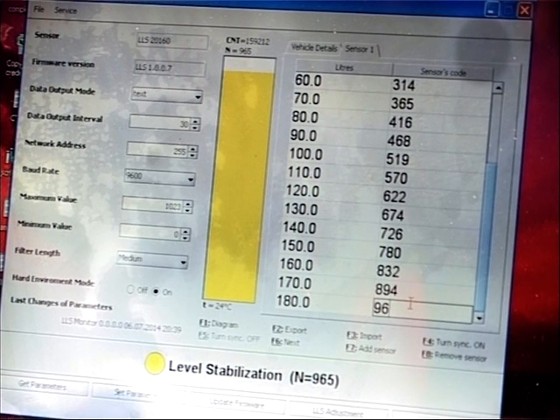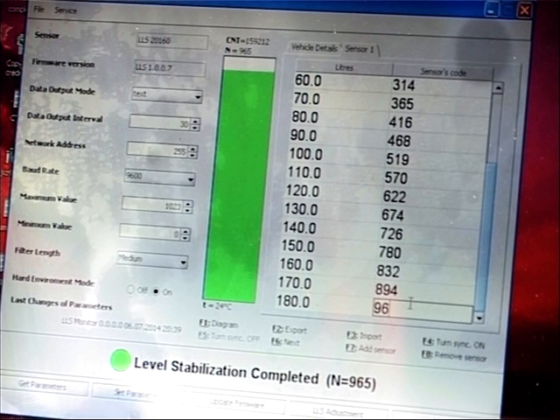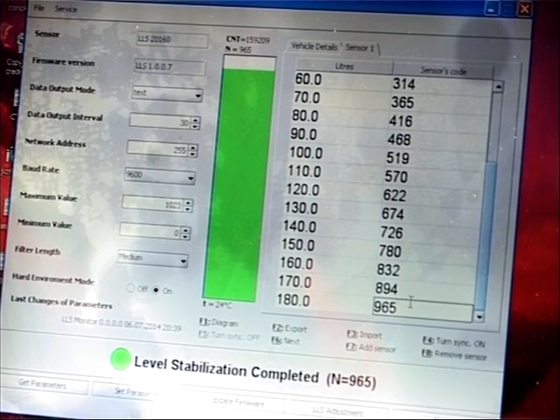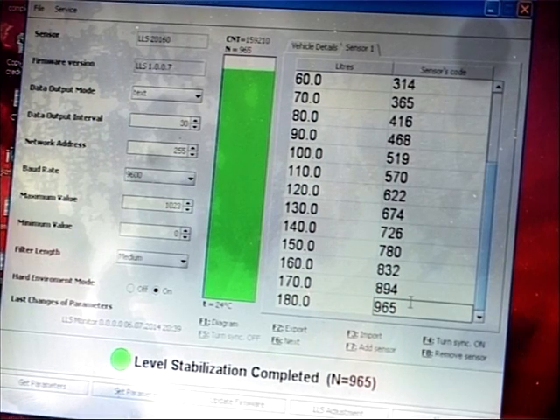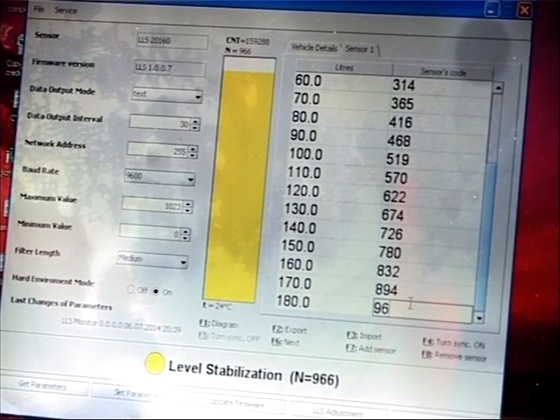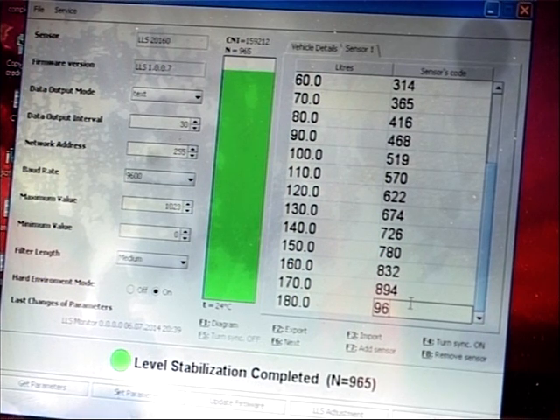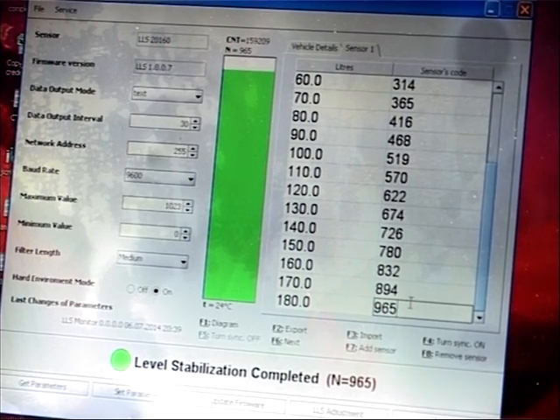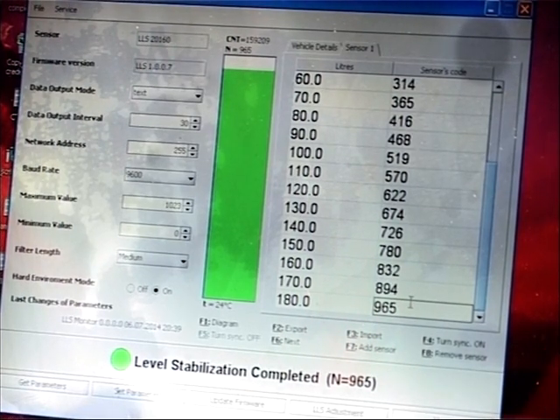Now, the number of calibrations will depend on the type of tank you're dealing with, because we understand tanks are of different shapes and sizes. But this level sensor is designed to work in all manner of tanks. On the left column, it's the column for liters, the amount of liters that we're going to put until the tank fills up. On the right-hand side are the sensor codes that are generated after every 10-liter fill.